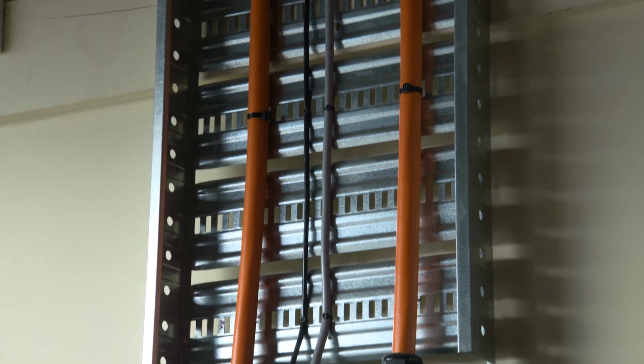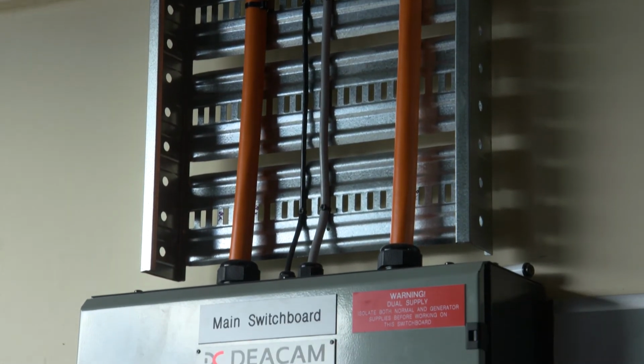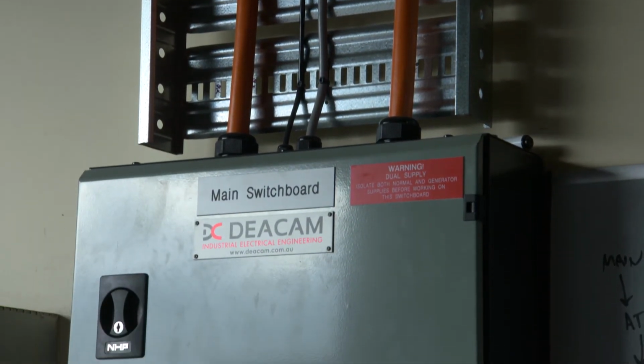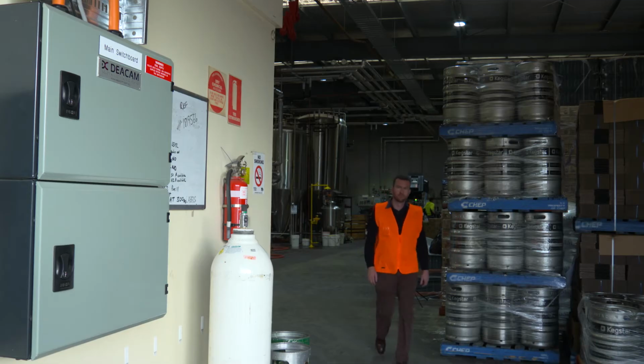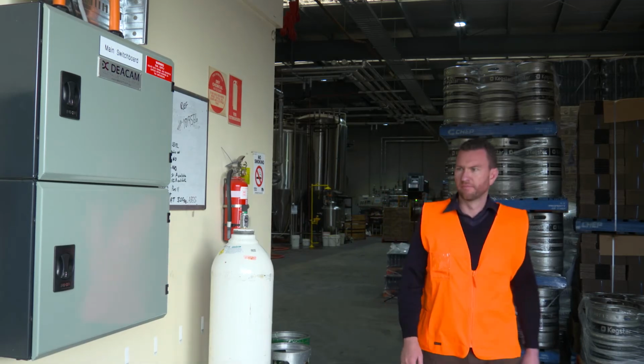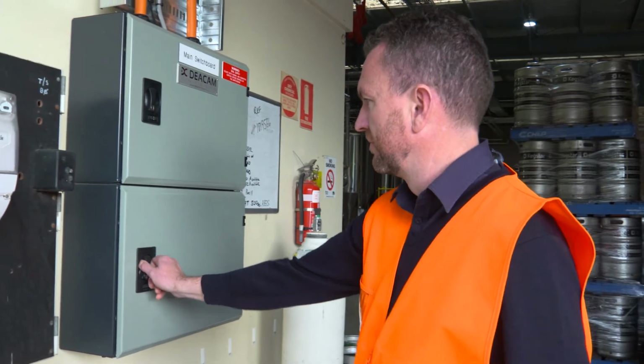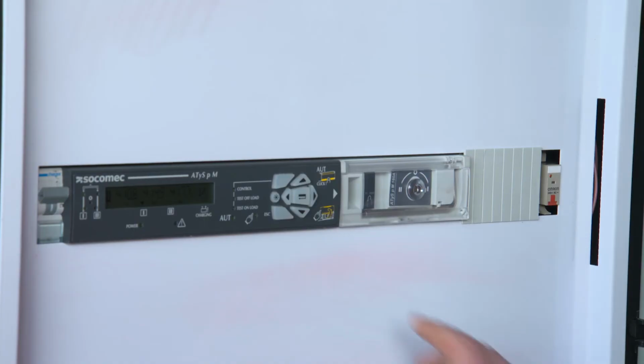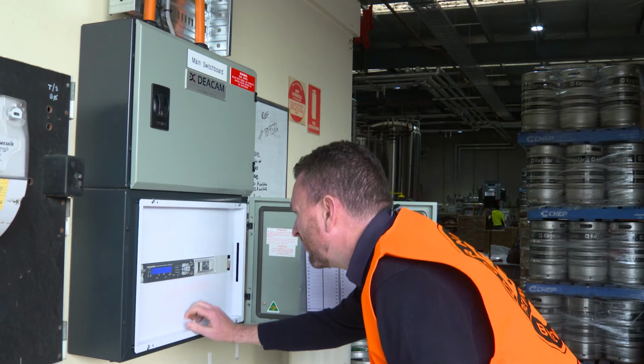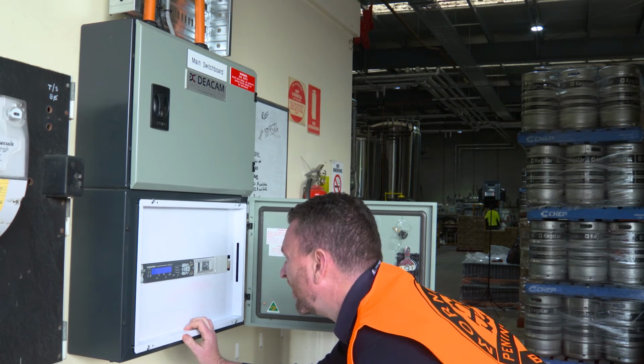The batteries really are providing peak load protection for the brewery. We know there are times this brewery runs as low as 40 amps a phase, and that's often. It's just those peaks that really bring a lot of businesses unstuck, and that's where batteries are fantastic. This system forces power in when we need it, and when we have surplus power within the facility, we charge the batteries up.